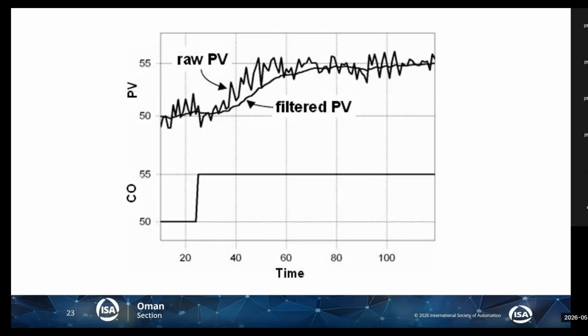Then we have something called noisy signals. When the instrument is transmitting the signal from the field to the DCS, especially flow signals, they may have some noise. And you can see noise is like this variation, and this variation is not a change in the flow. It is only noise. But it's affecting because the controller will think this is a change in the flow and the valve will start hunting. It will react on each change, or it will not give you an accurate output, because all these variations will be involved in the PID algorithm, and they are not correct.